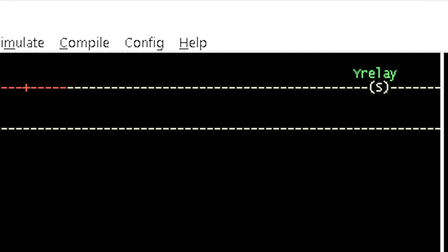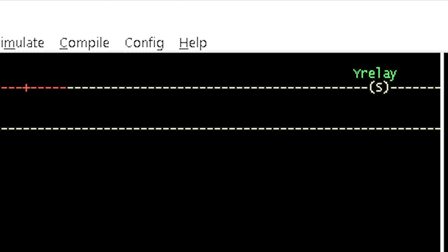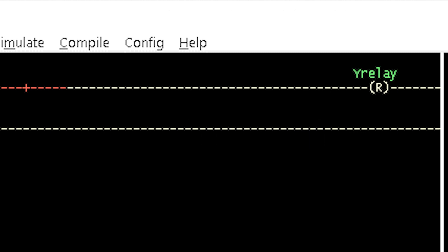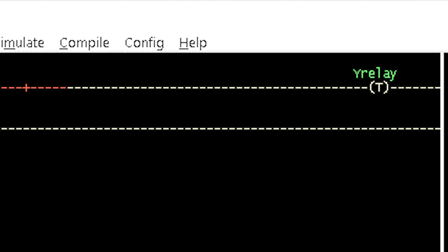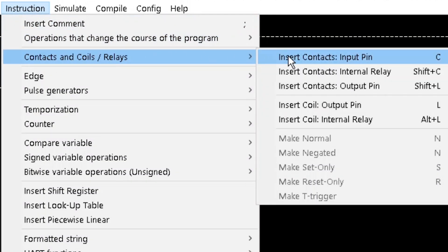Other types of coil are the set only, whose function is to set the output of the coil to only true if the logic result is true; the reset only, used in combination with the set only instruction, whose function is to set the output variable from true to false when the logic result is true; and the T-trigger, used to detect a rising edge of a logic output. The T-trigger coil output will be true when it detects a rising signal edge and will become false when it detects another rising edge. These instruction elements can be inserted into a ladder diagram from the contacts and coils/relays option of the instruction menu.